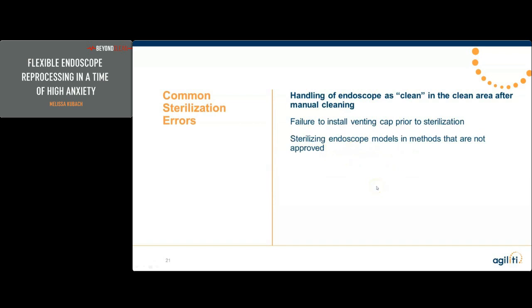And once again, sterilizing endoscope models in methods that are not approved. I don't see this that often, but I occasionally run into a really old scope in a facility where all of their models are approved for peroxide vapor or gas plasma. And that model isn't, and it manages to make its way in there, but it usually doesn't last very long. It doesn't last a lot of procedures, but you always have to make sure you know that endoscope is approved for that sterilization method.